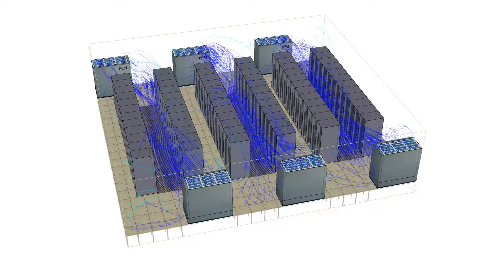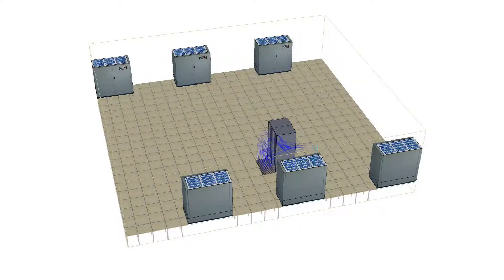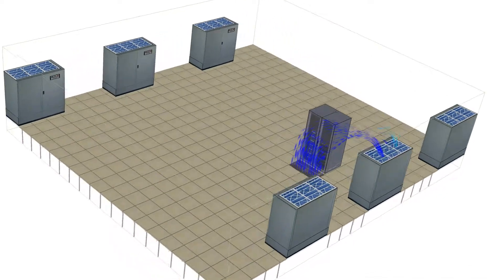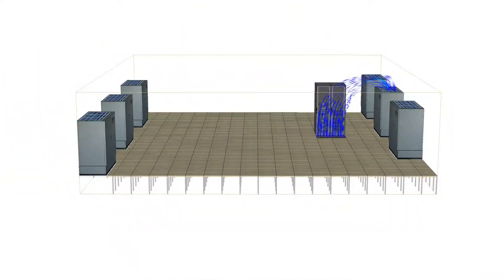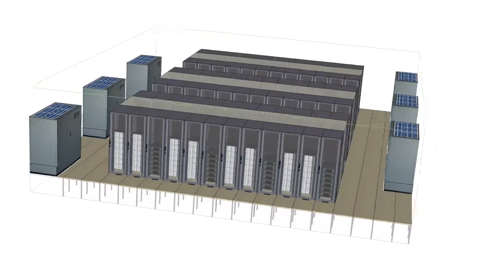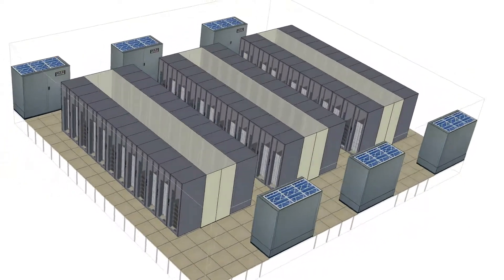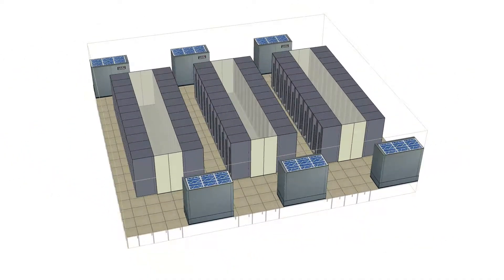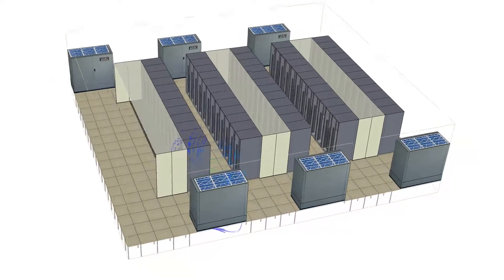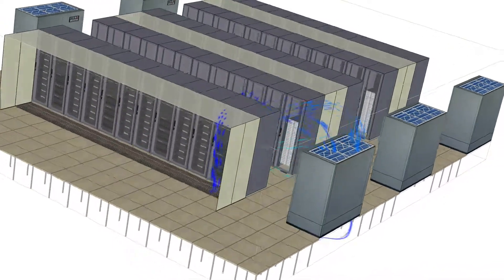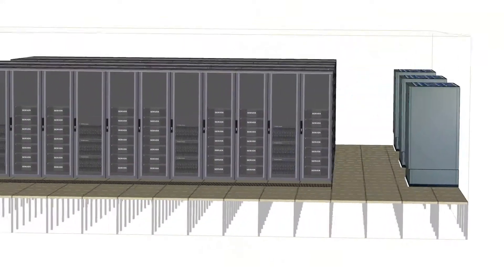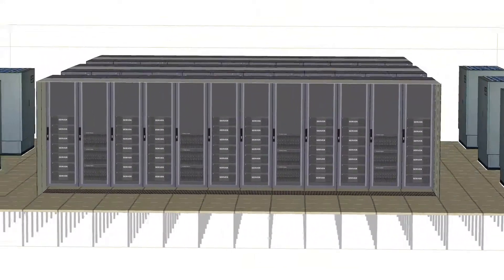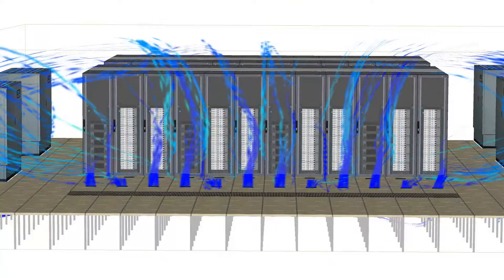Bypass airflow can occur for several reasons. In an open room, ACUs may pull air directly from the floor grills. In a contained cold aisle, air may be forced through gaps in the cabinets, bypassing the equipment. Another common source of bypass airflow is cable penetrations and other poorly sealed floor holes.